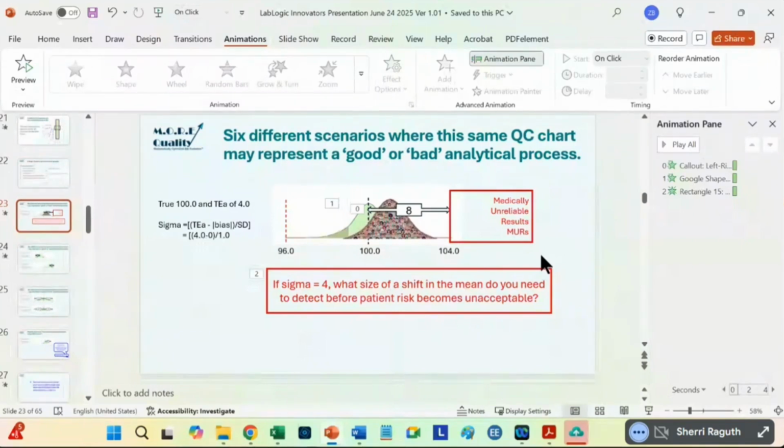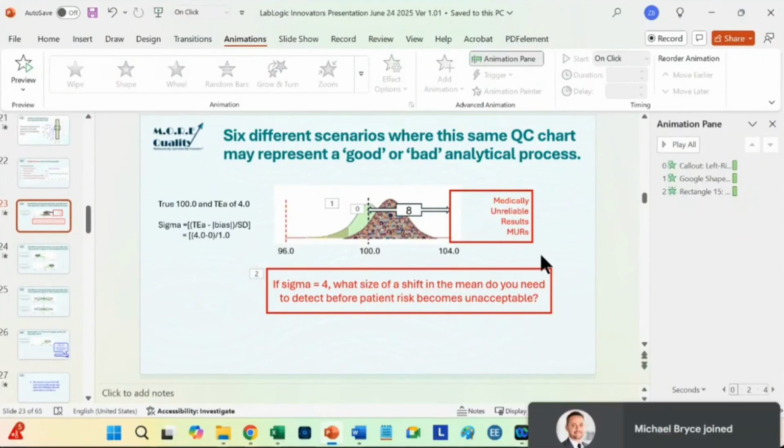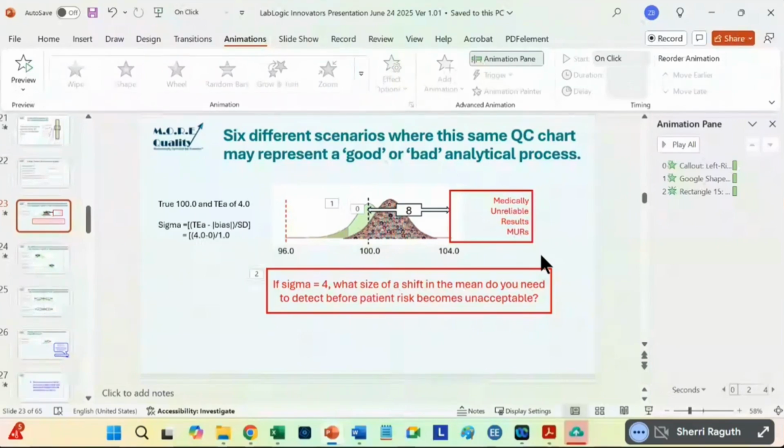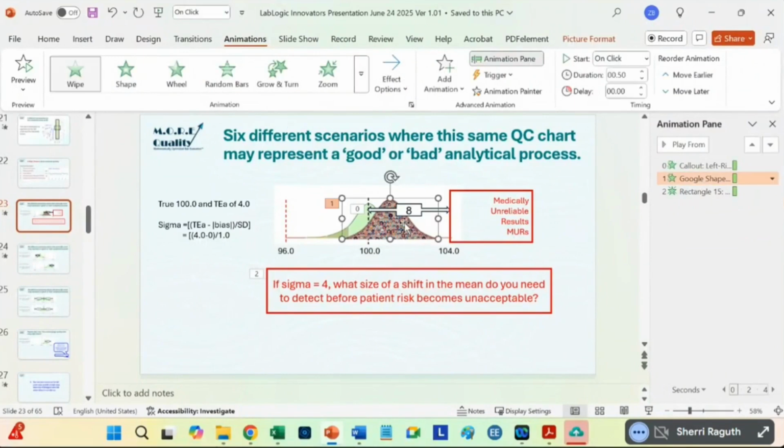Do you set allowable error limits? Yes? Okay. Do you measure total error then? No. Actually, we don't know too much. Okay. Are you mistaking allowable error limits for QC chart limits? We're only checking the Westgard rules. Okay. And that's what you're missing if you're not looking at this: is my method acceptable? Okay.